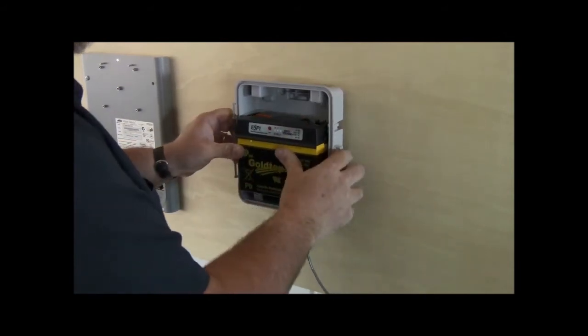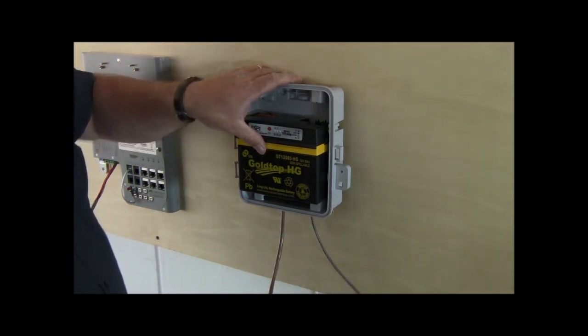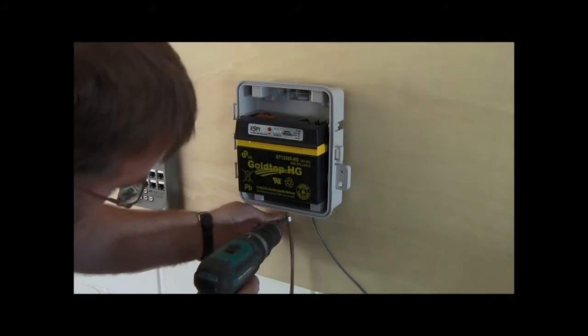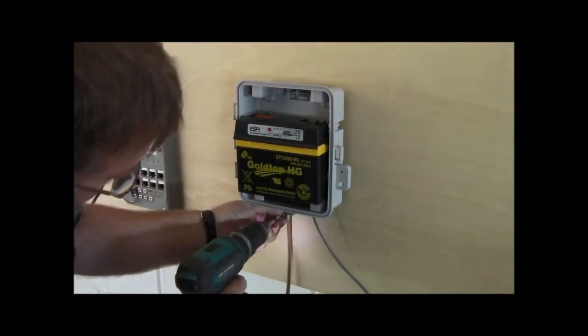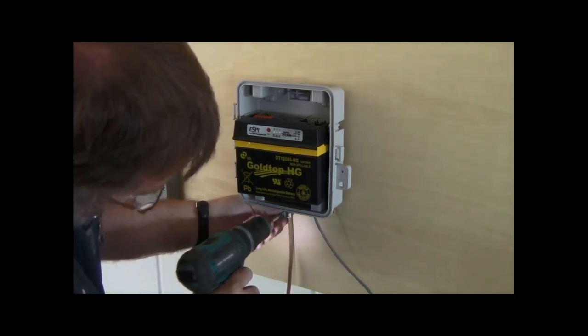Turn the battery and electronics around. Slide the electronic circuit enclosure and battery into the two slots in the enclosure. Push the cables up into the enclosure so the outer jacket is near the bottom of the battery. There should be plenty of wire to allow the unit to be removed and the battery replaced in the future. Install strain reliefs to the cable so the wires are not pulled from the unit.